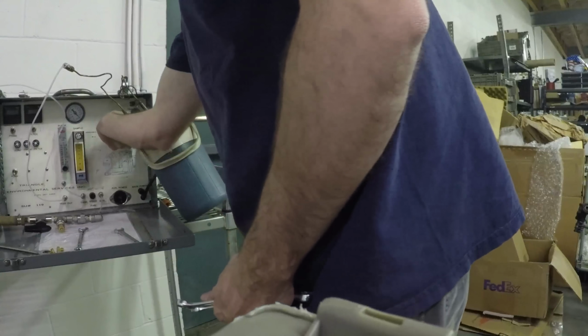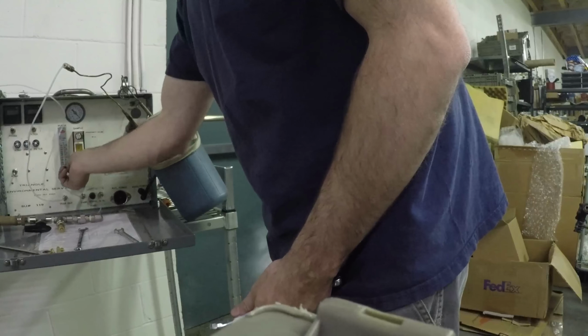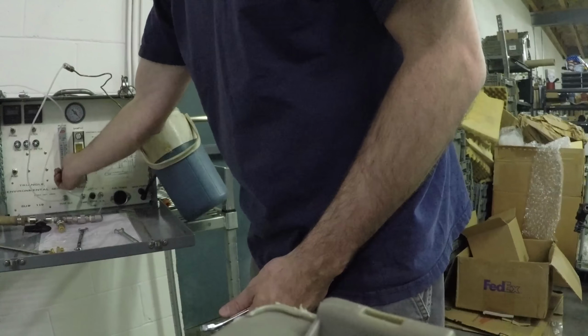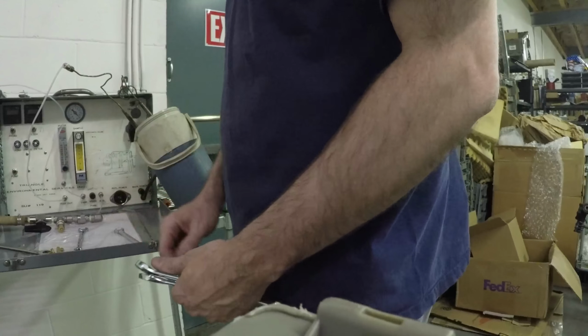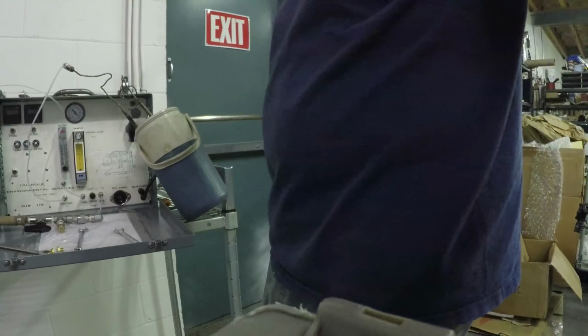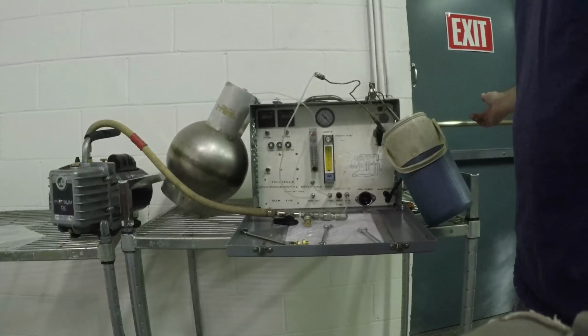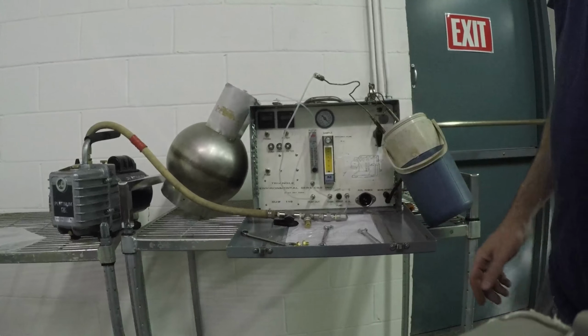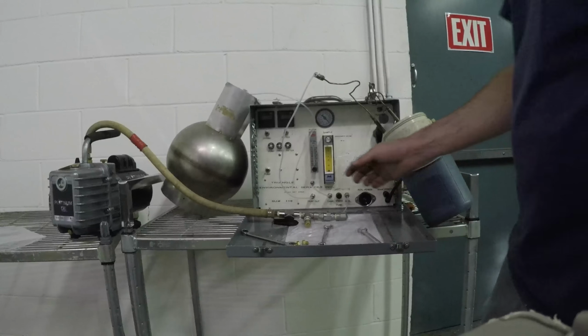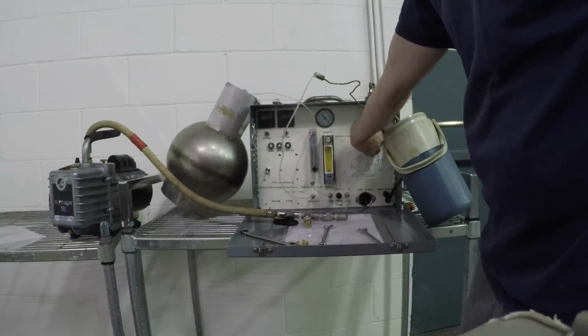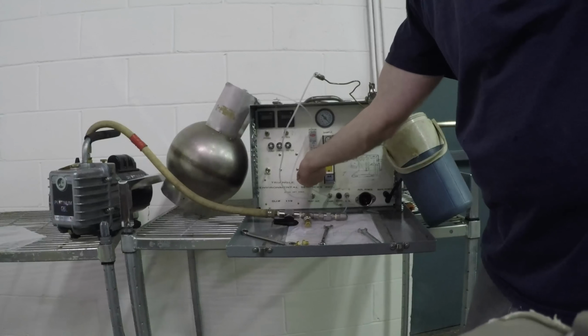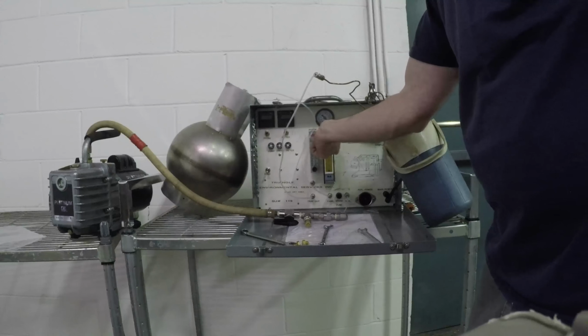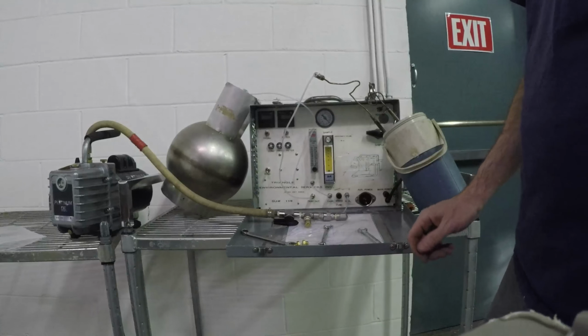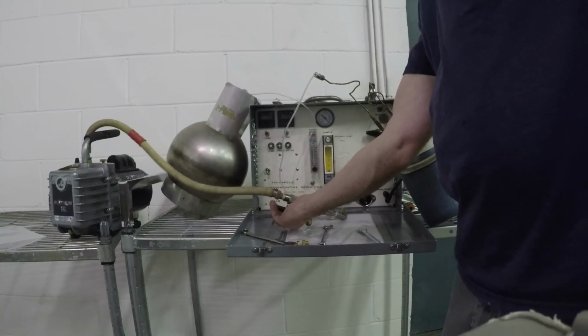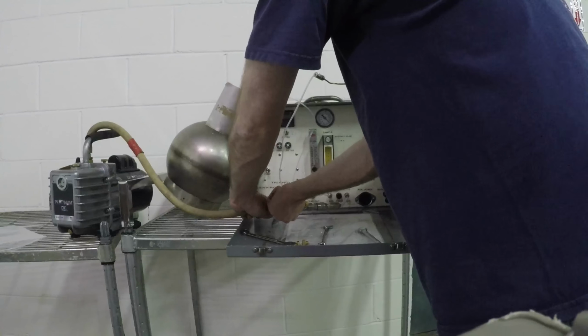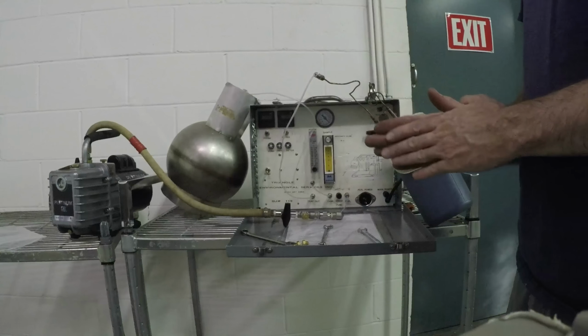At which time, you turn this to purge, turn on your purge pump, open that. This purges all the atmospheric out of the line. Let it run for about a minute or so. Turn that off, close your purge, close your sample. Make sure that is turned off. You are now ready to sample.